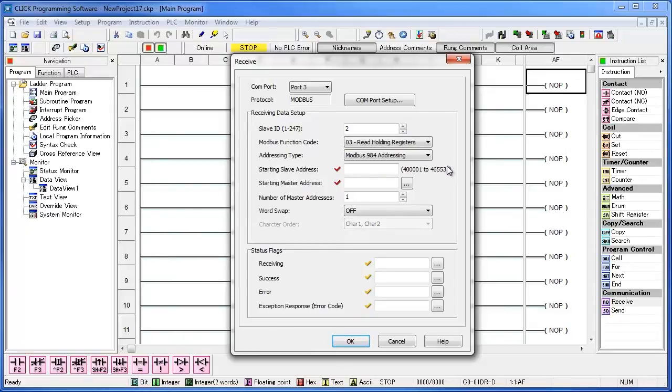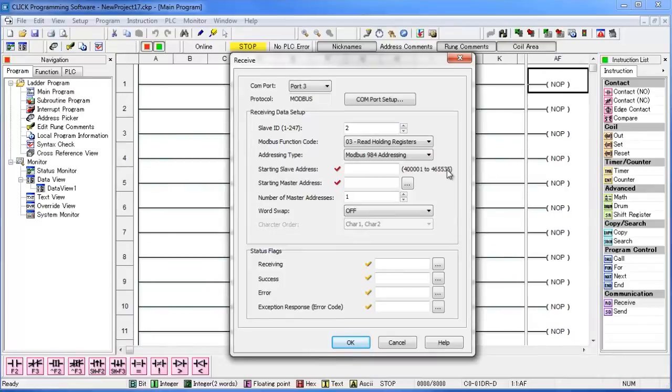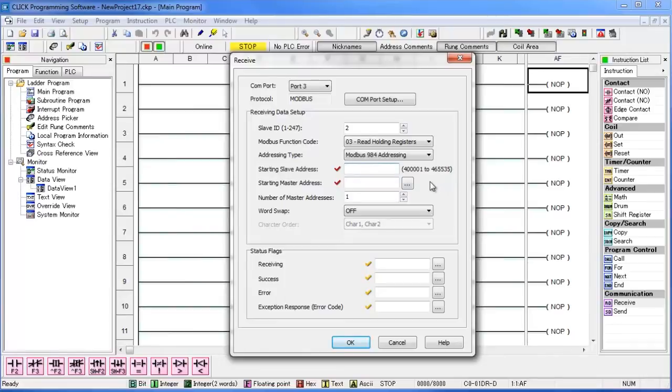Now we need to put in a slave address. You can find all of the slave addresses for the SOLO in the manual under Chapter 7. For our example, we want to read the temperature from the SOLO into a data register in the CLICK. The slave address in the SOLO that holds this data is 4,097.